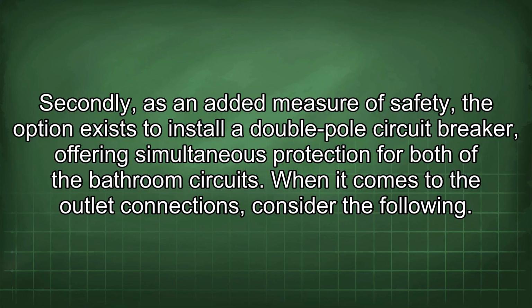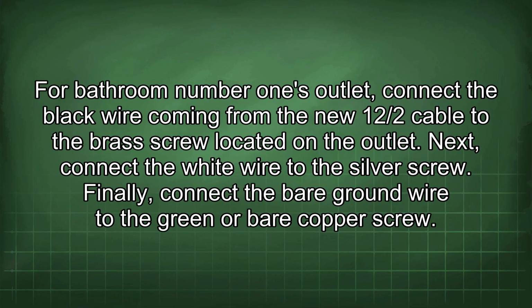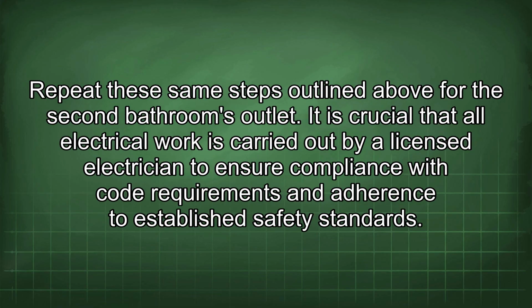When it comes to the outlet connections, consider the following. For bathroom number 1's outlet, connect the black wire coming from the new 12/2 cable to the brass screw located in the outlet. Next, connect the white wire to the silver screw. Finally, connect the bare ground wire to the green or bare copper screw. Repeat these same steps outlined above for the second bathroom's outlet.